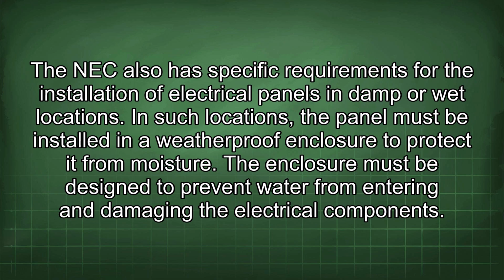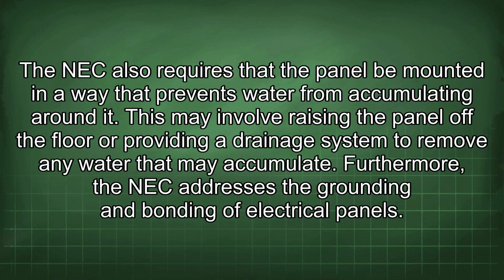The NEC also has specific requirements for the installation of electrical panels in damp or wet locations. In such locations, a panel must be installed in a weatherproof enclosure to protect it from moisture. The enclosure must be designed to prevent water from entering and damaging the electrical components. The NEC also requires that the panel be mounted in a way that prevents water from accumulating around it. This may involve raising the panel off the floor or providing a drainage system to remove any water that may accumulate.